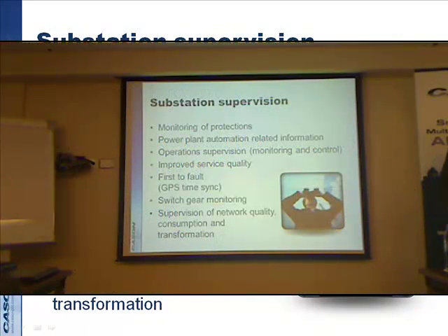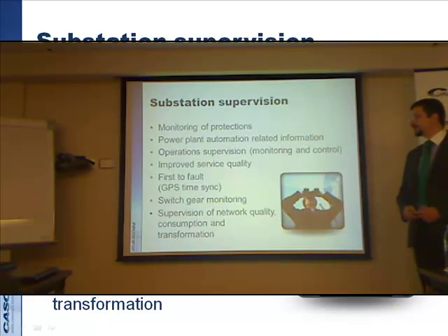We are able to implement a so-called first-to-fault system, which is quite unique. By using GPS time synchronization, usually in an electrical network, if something goes wrong, basically everything goes wrong because all the systems go down. Mainly the protections make sure nothing is overloaded or damaged. But to find what was the first thing that faulted, it's necessary to have time synchronization in the network, so we can find out what was the original cause that led to the problem.